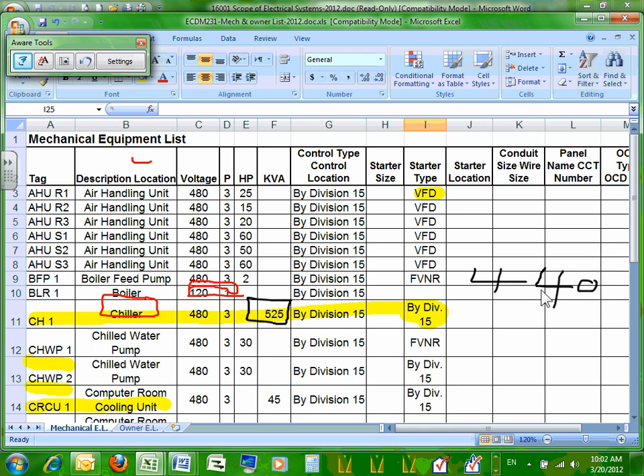The trouble is chiller manufacturers play games with kW per horsepower, and of course, depending on your power factor, that translates into KVA. I have to size my wires for the amps and my gensets for both kW and KVA. But they'll say we're 0.65 kW per ton, and they're not even necessarily giving me the horsepower. They're giving me the tons of the chiller. And okay, what's the horsepower? Can't find it. It's 746 watts per horsepower, but then you have to factor in efficiency.